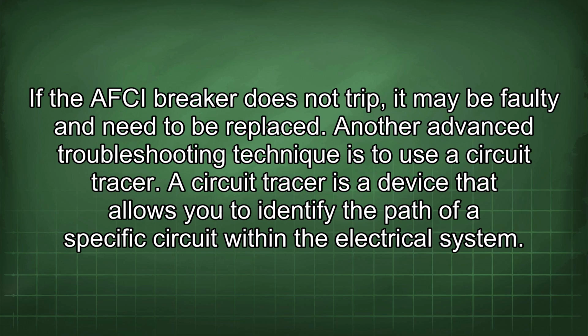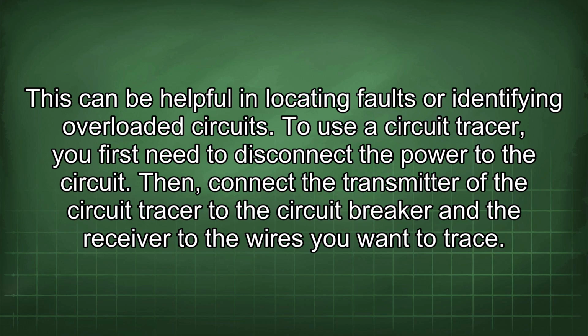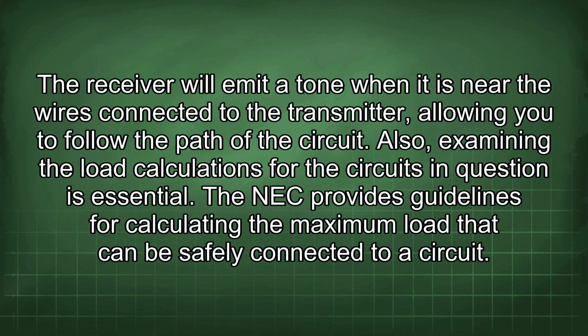Another advanced troubleshooting technique is to use a circuit tracer. A circuit tracer is a device that allows you to identify the path of a specific circuit within the electrical system. This can be helpful in locating faults or identifying overloaded circuits. To use a circuit tracer, you first need to disconnect the power to the circuit. Then connect the transmitter of the circuit tracer to the circuit breaker and the receiver to the wires you want to trace. The receiver will emit a tone when it is near the wires connected to the transmitter, allowing you to follow the path of the circuit.